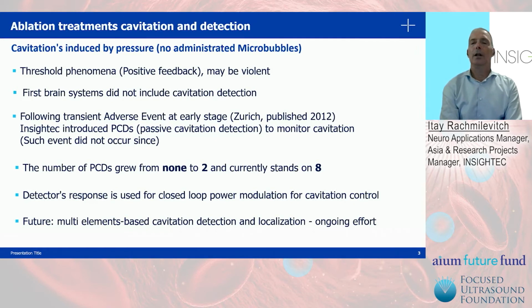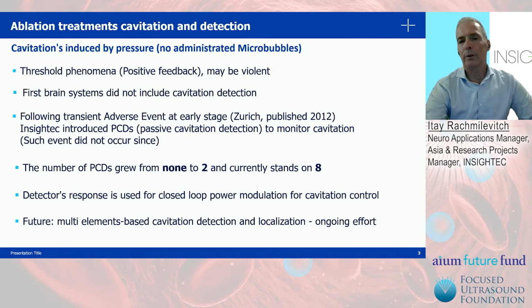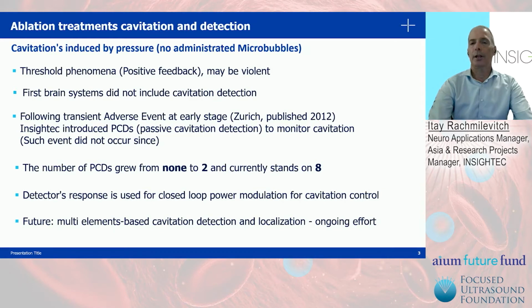Now it stands on 8. And in some systems, we use even higher numbers. You will see it in the coming slides. The detector's response is actually used to control the cavitation in order to keep the sonication safe.